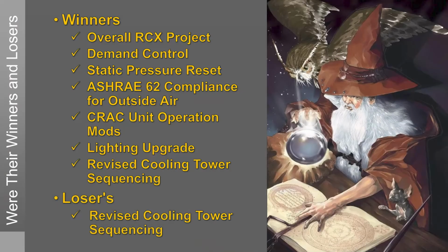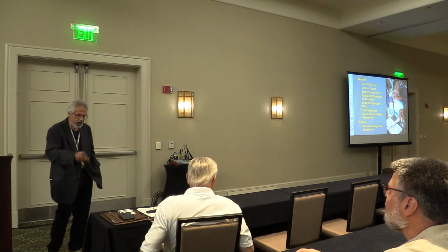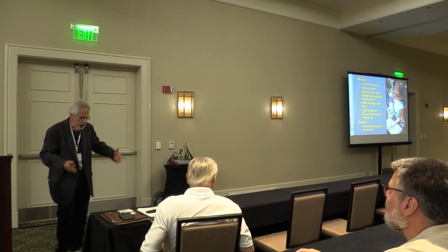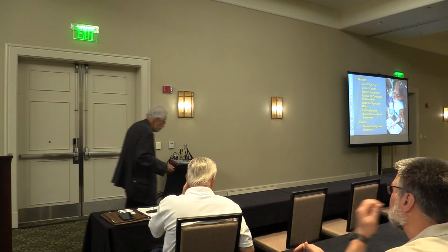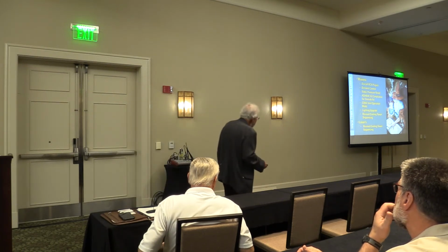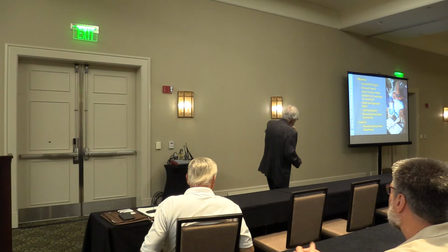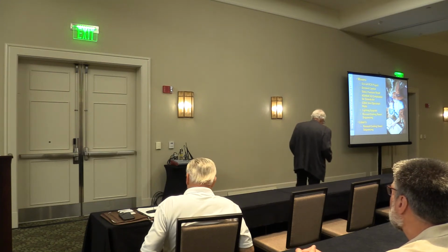So what were the winners? The winners were the overall retro-commissioning process, obviously demand control - nobody's in the building so we're not saving any air, we're still putting all the air in. ASHRAE compliance to make sure we did everything with outside air. They had some things with CRAC units running multiple, and I said we could probably make it work. We had to do some modifications to how their plumbing was in the floor, but real minor things. And they did the lighting upgrade, and then revised the cooling tower sequencing.